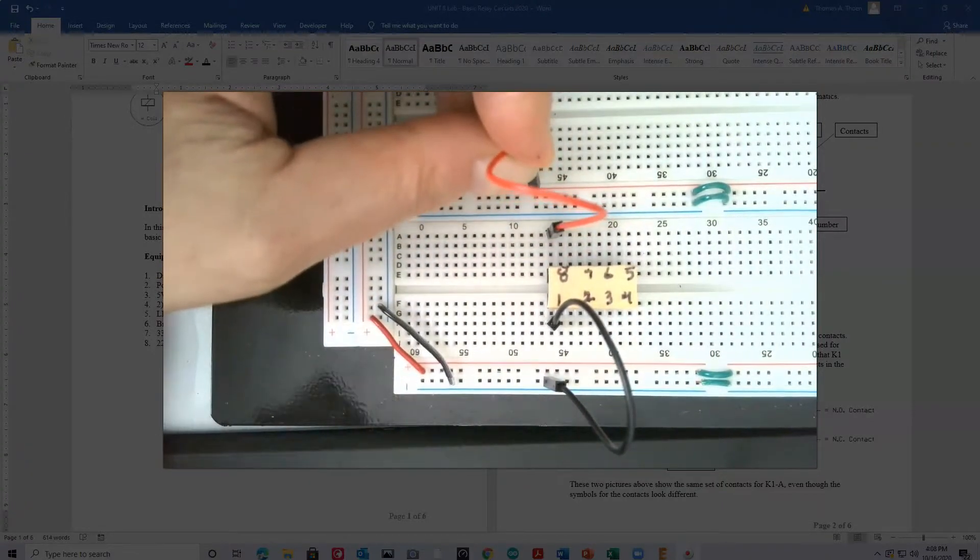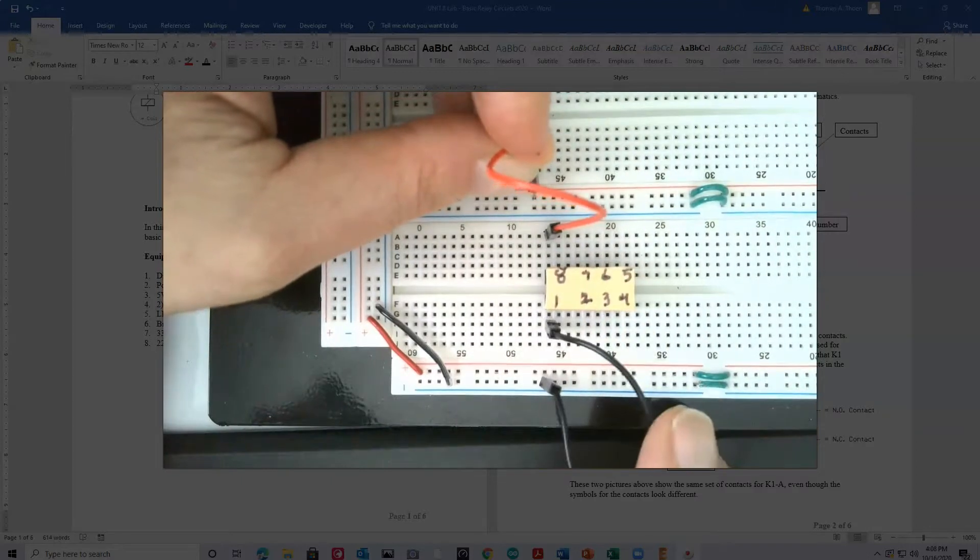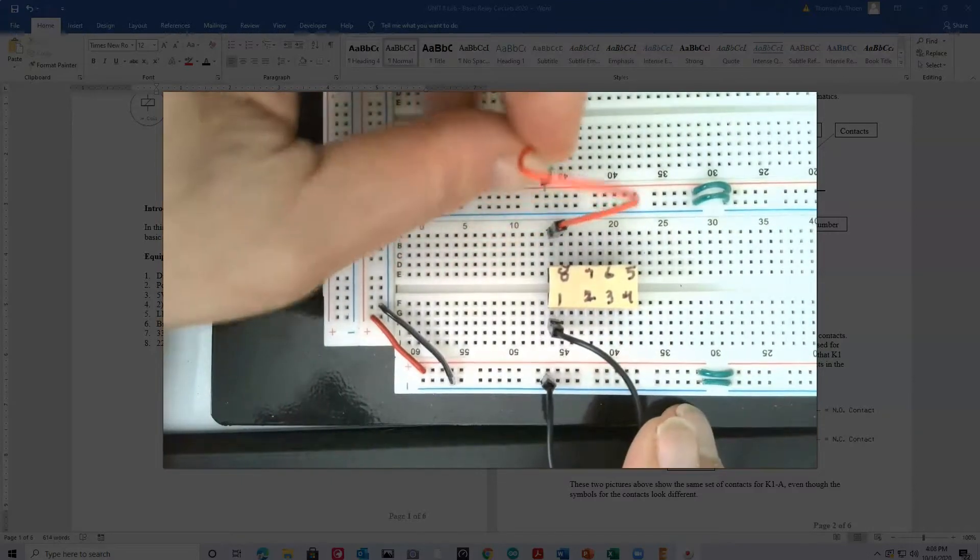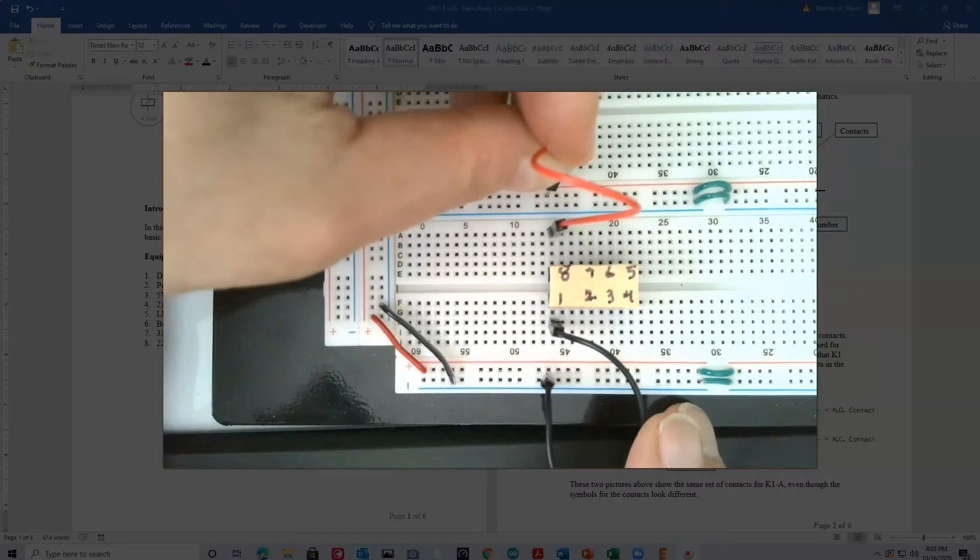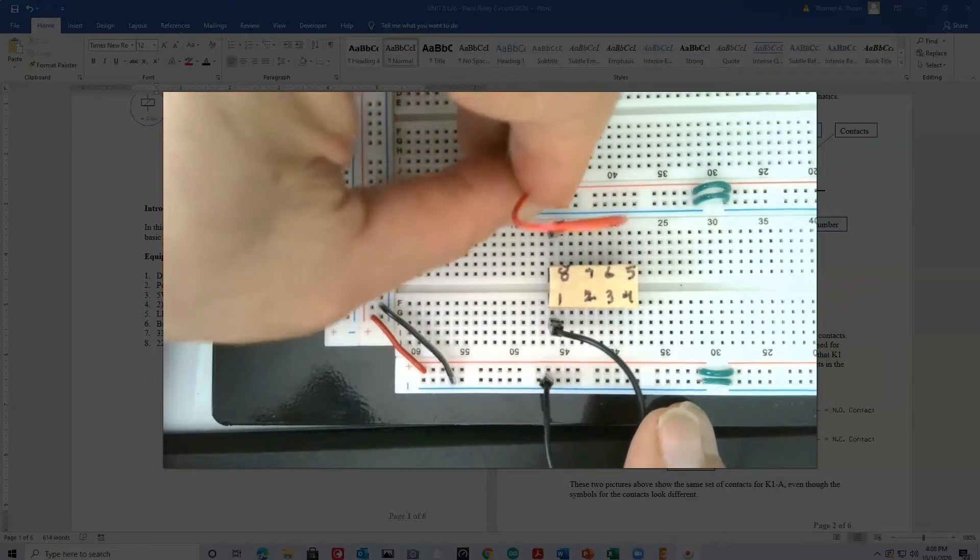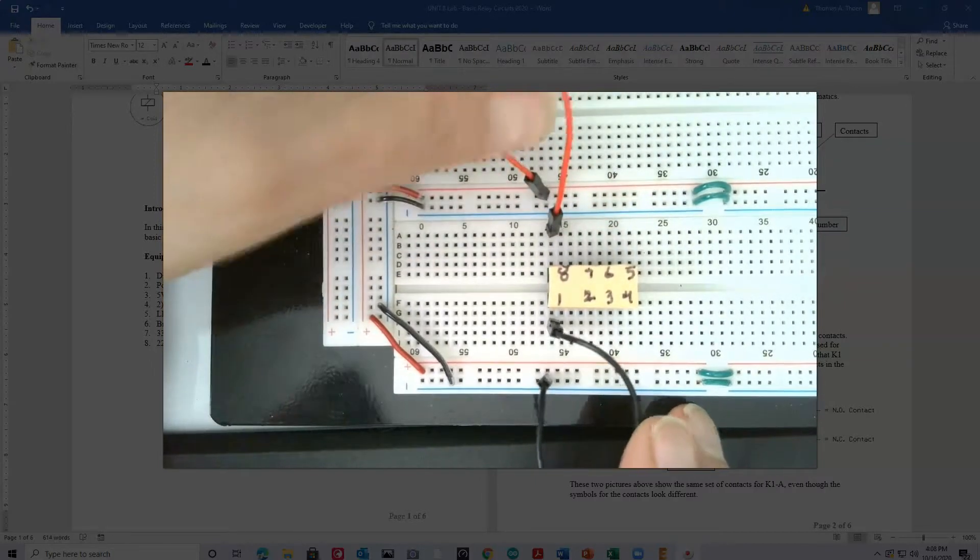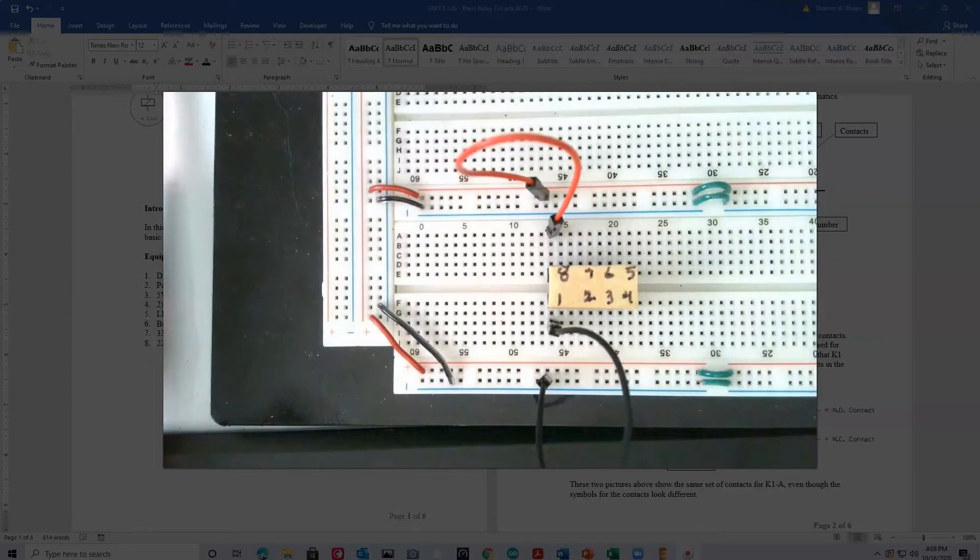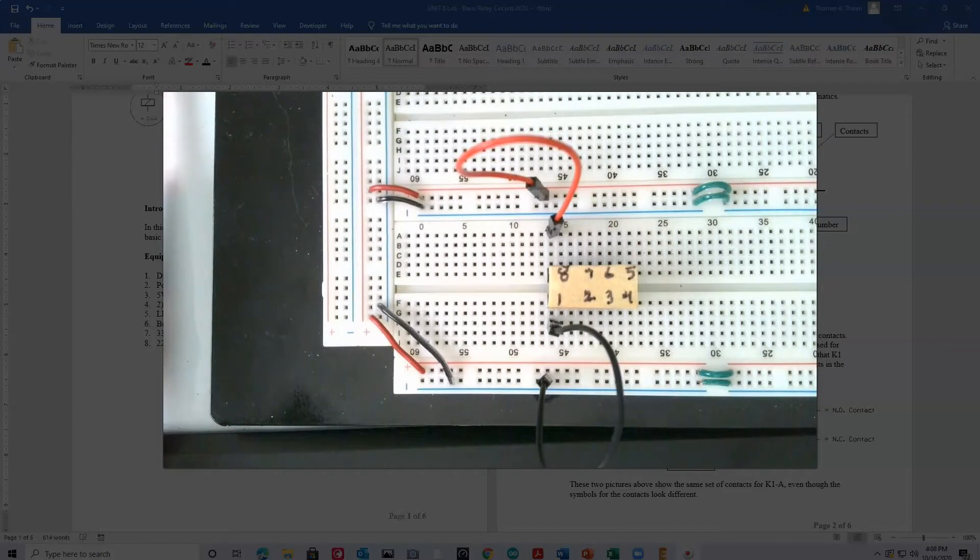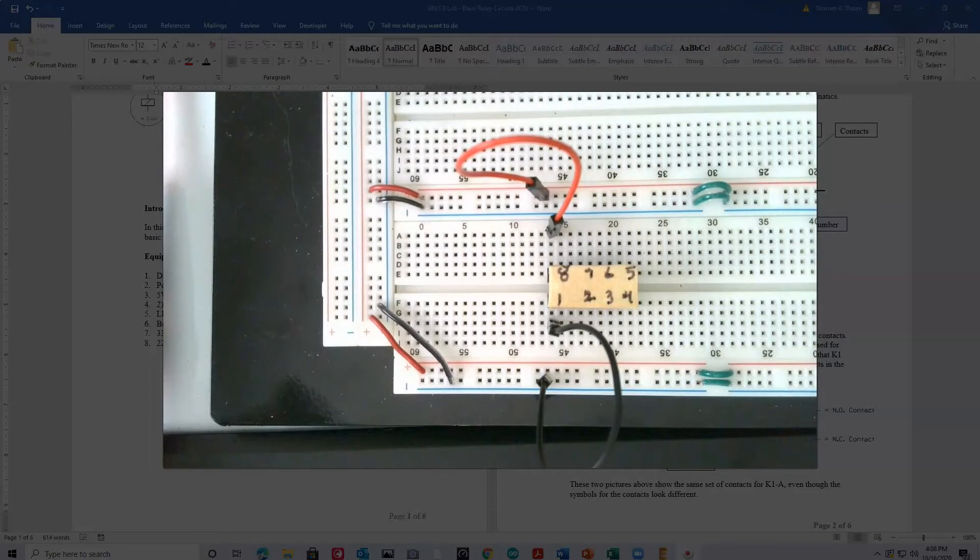Now, I don't know if you're going to be able to hear this in the video or not. But when I'm making this electrical connection here, you can hear this little click. That is, you're actually hearing the coil activate the armature, and the armature is pulling in. That's what's making that sound. And I would suggest doing that, just wire up this really basic circuit, just to test it and make sure that it's working.